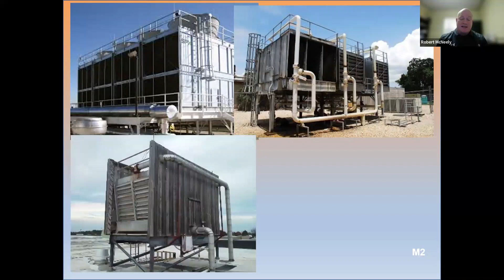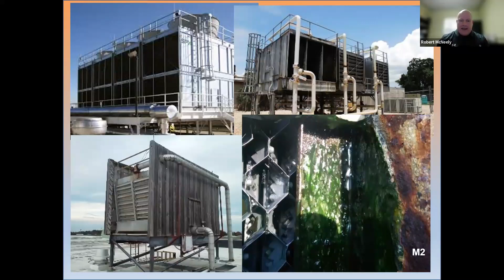Everybody thinks about cooling towers when they think about Legionella, sometimes that's the only thing they think about. But you could have a cooling tower hitting all its parameters, even having low HPCs, heterotrophic plate counts, and still have huge concentrations of Legionella. The water could look pristine and still have high concentrations. And then a bad-looking one might not have any at all.